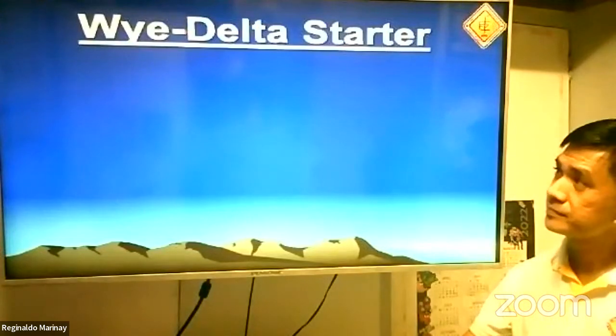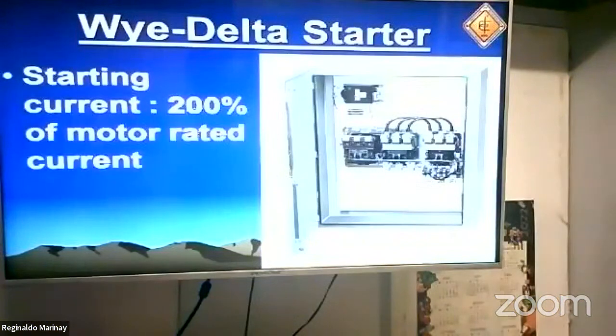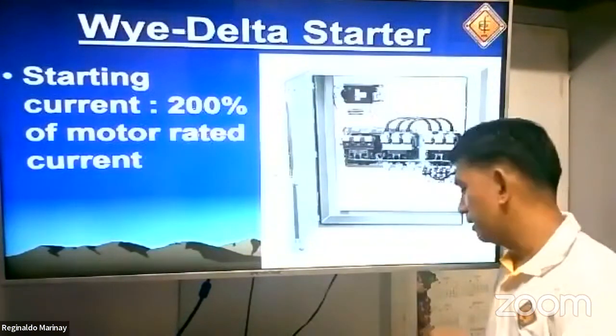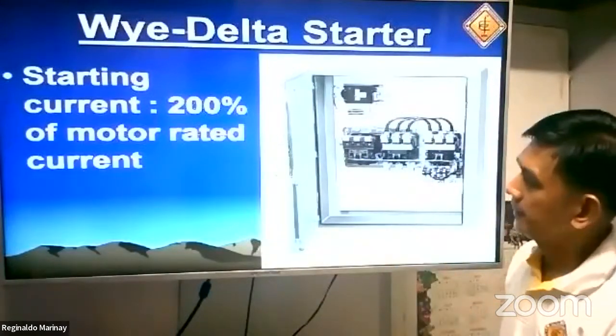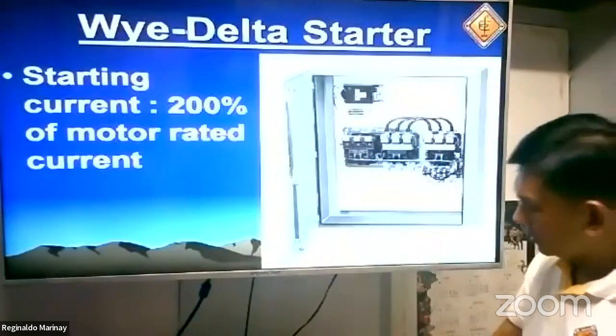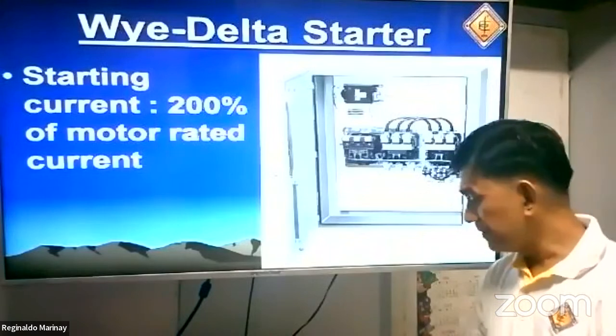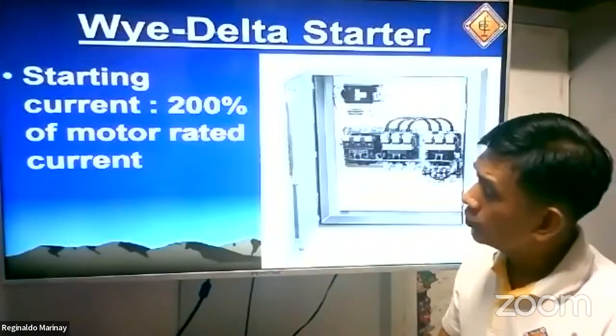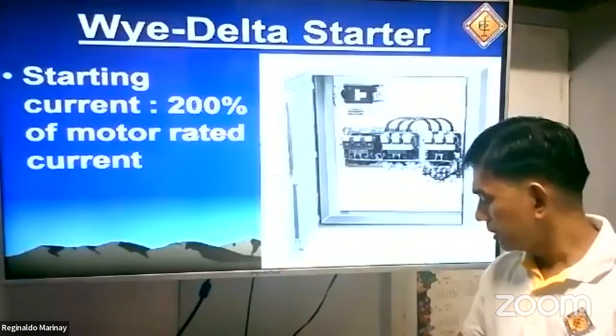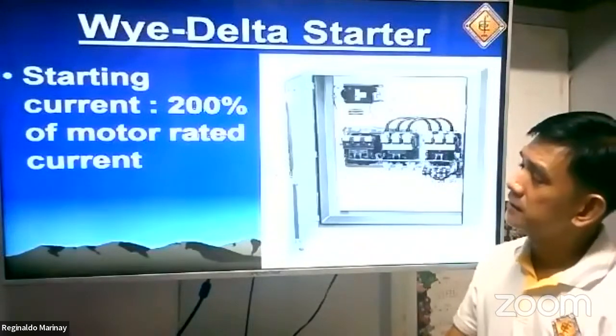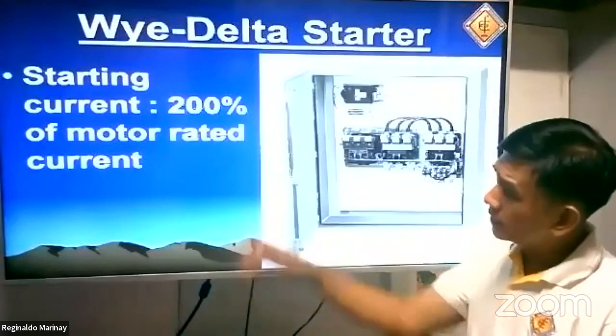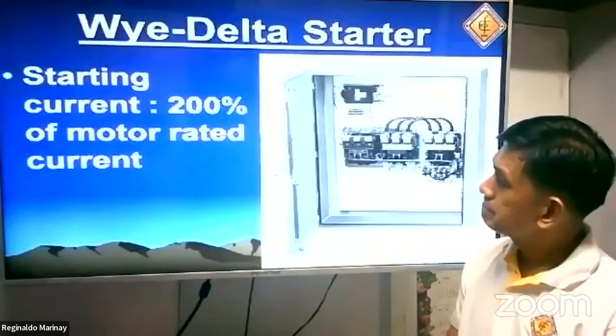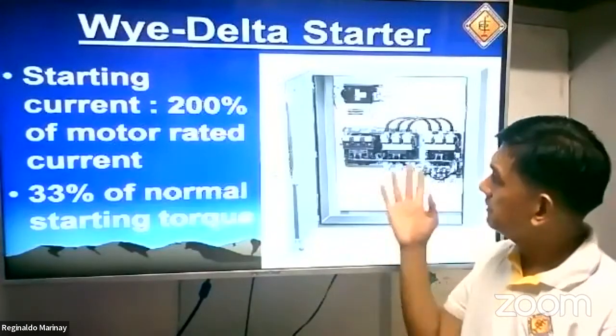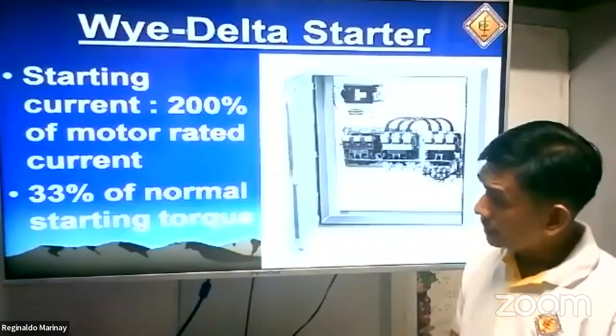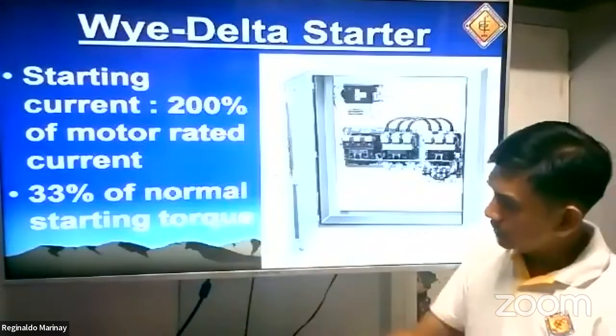We will go to the last type of motor starter for today. Actually, in our special training or webinar, we'll discuss more types of motor starter. We'll go to the Y delta starter. This is being given by our authority here in the Philippines, the TESDA, in the NC2 National Certification regarding motor control. The starting current is 200% of the motor rated current. Basically, this is the cheapest motor starter that we are going to study today. Then you're reducing the starting torque.